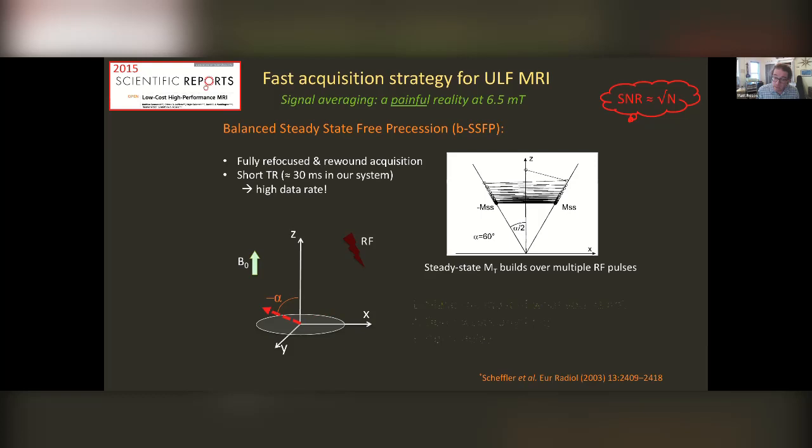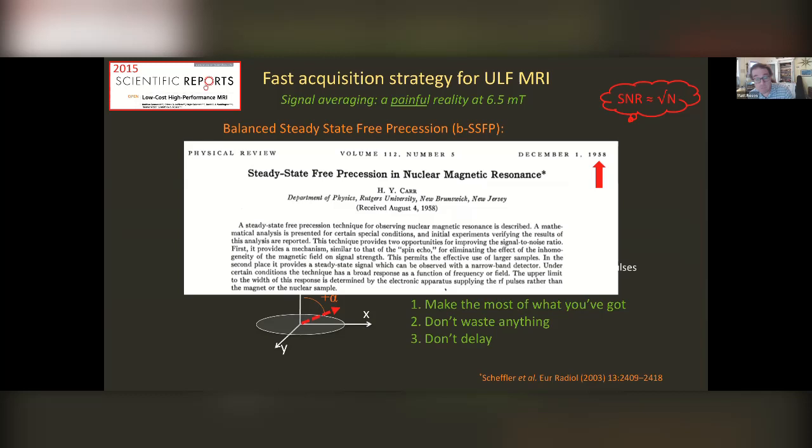And so this gets us to the rules of low field magnetic resonance, which is, when you have low SNR, make the most of what you have. So large tip angles, sample all your magnetization, don't waste anything. So typically crushing is kind of a bad idea, and don't delay, right? If you have long dead times, you're not taking data. Of course, Herman Carr knew this in 1958 when he wrote down SSFP.